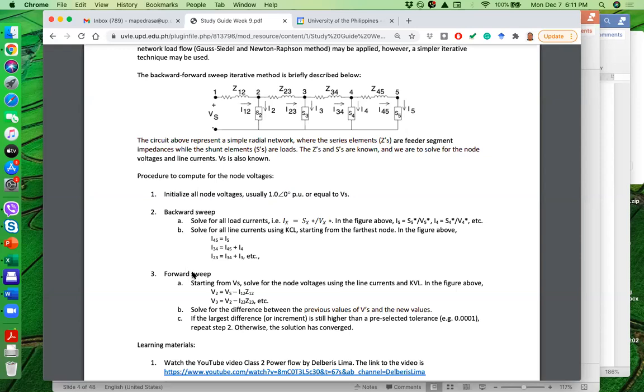The second half is the forward sweep, which involves solving for voltages using KVL. For the forward sweep, we start at the substation and work our way down to V5. Since Vs is known, we can solve for V2: V2 equals Vs minus I12 times Z12. After initialization, V2 was one angle zero, but after the forward sweep we get new values for V2.